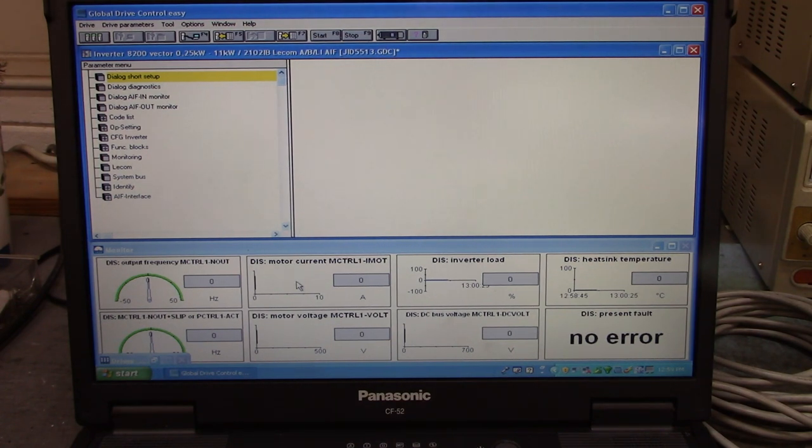That we can pull the parameters off of that microcontroller without line voltage applied to the drive to power it up. That's nice. Now when I get to the house I'll show you my drawings of the power supply sections and how you can power up your blown up Lenze inverter drive. Not hard to do, not hard to do at all.